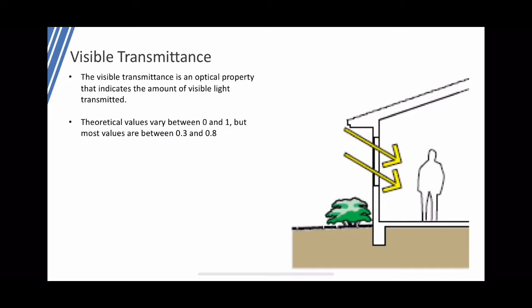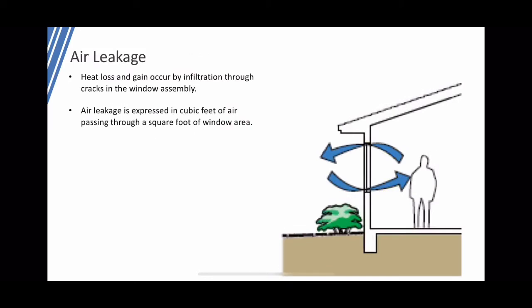Visible transmittance is an optical property indicating how much visible light passes through a window, with a theoretical range of 0 to 1 — typical values fall between 0.3 and 0.8. Air leakage refers to heat loss and gain by infiltration through cracks in the window assembly, expressed in cubic feet of air passing through a square foot of window area per minute.